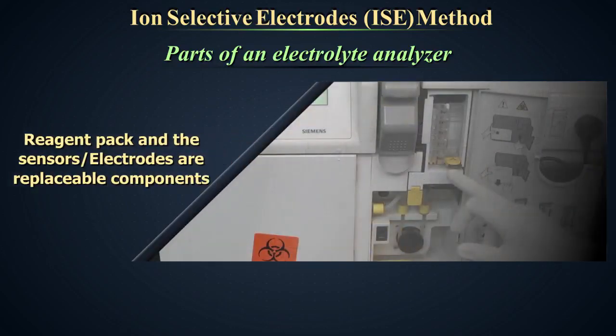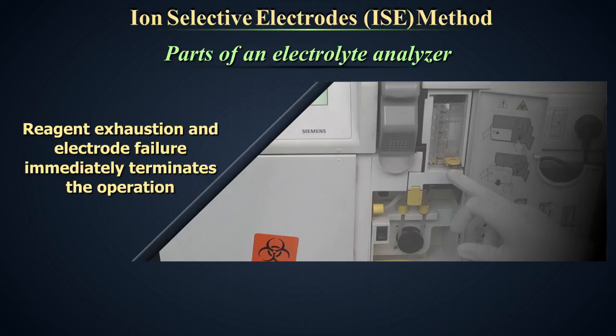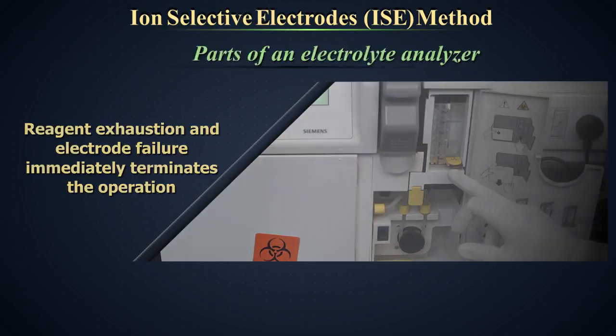The reagent pack and the sensors are replaceable components of the instrument. Spares for both should always be kept as a backup, as both are critical for running the samples. Reagent exhaustion or expiry and electrode failure will immediately terminate the operation. Hence, to ensure smooth functioning, always keep these components in backup.